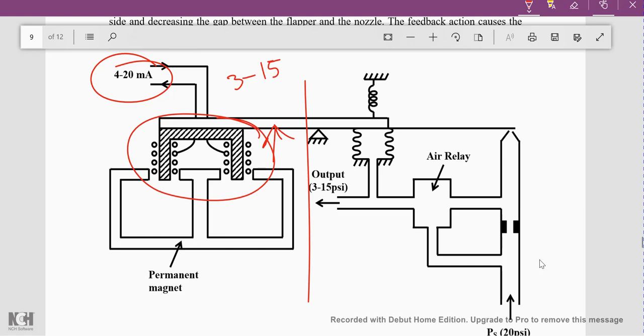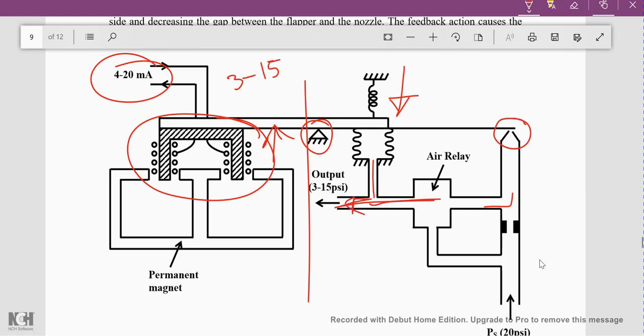When the current increases, the repulsive force increases and the beam moves away from the fixed permanent magnet. With respect to the fixed fulcrum, this side of the beam starts coming downward, experiencing a downward force. Due to this, the nozzle will be closed — less opening will be available — as the flapper comes closer to the nozzle area, causing the pressure here to increase.